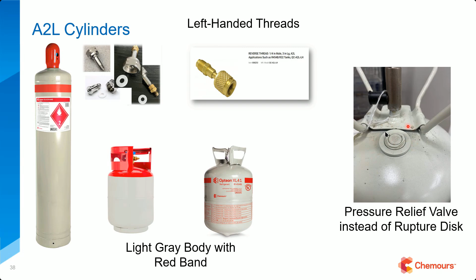Now, moving forward, you're going to see a different safety device. We've always had ruptured discs in the past. How do ruptured discs work? It gets above the pressure temperature allowed for that refrigerant tank, and this pops and blows the whole charge. Now, where I'm at, that's never happened, very rarely if ever.